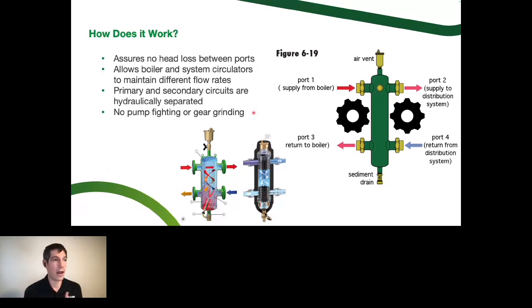There are a lot of different analogies to this. We're going to have a follow-up article that's going to run in the CMPX issue that's going to talk about this with a few more examples as well, if you need something that's kind of written to refer to. But that's what we're doing with primary secondary piping. There are 3 different ways that I'm going to describe that we can do this. This is a low loss header or a hydraulic separator. There are a bunch of different names for this device, but that's really all that we're doing, moving those 2 wheels so they're no longer touching each other. And I'll go through the different flow examples of what can happen inside of these devices as we move on.